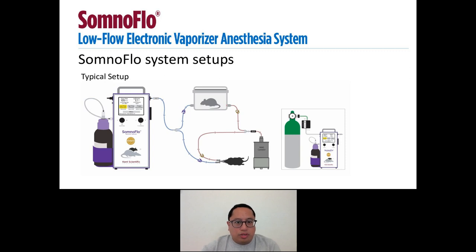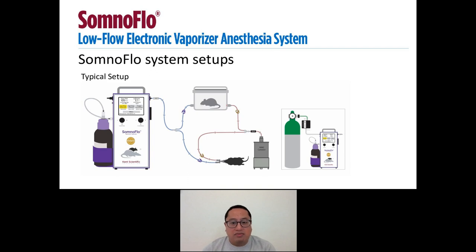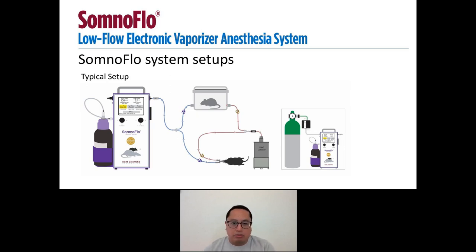Now we'll go through various SomnoFlo system setups. This diagram displays a typical setup with an induction chamber and a face mask using the two accessory adapter. The anesthesia outlet marked in blue is the inspiratory line, which comes from the SomnoFlo and splits into two branches leading to either the induction chamber or the face mask. Leading out from the induction chamber and the mask is the expiratory line marked in red. This line passively carries waste gases to the WAG canister. If you choose to connect your SomnoFlo to compressed gas, the incoming pressure from the compressed gas tank must not be higher than 15 psi.